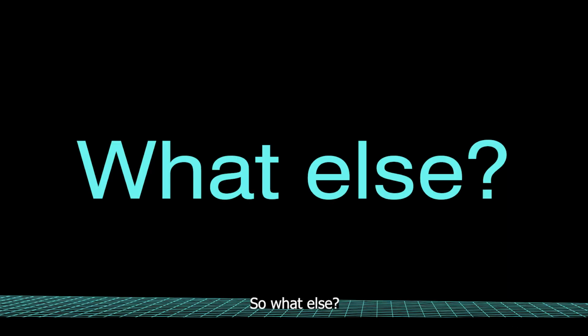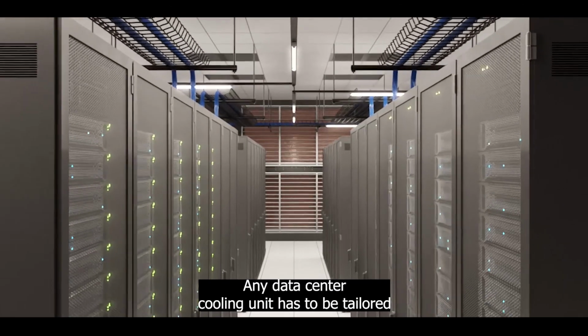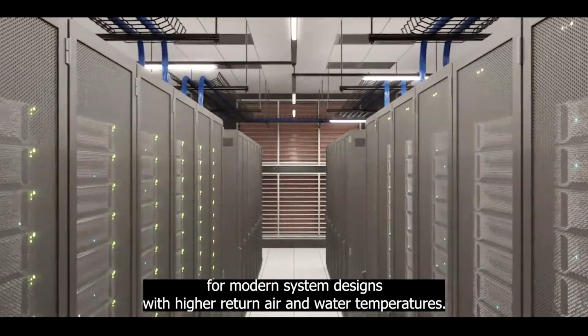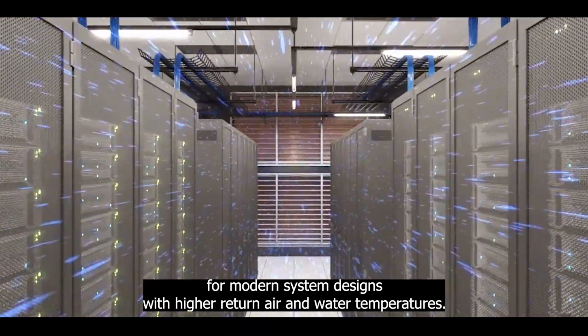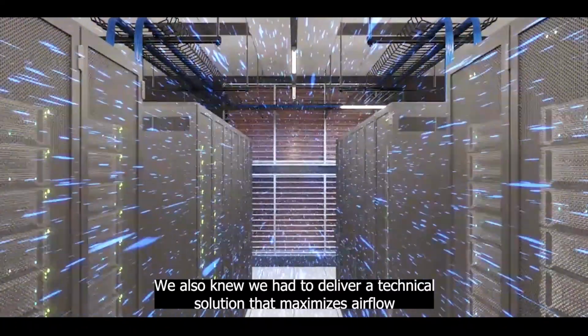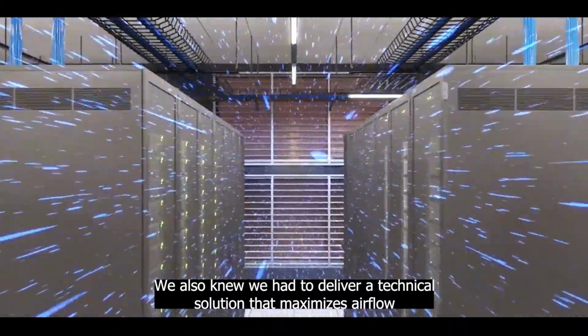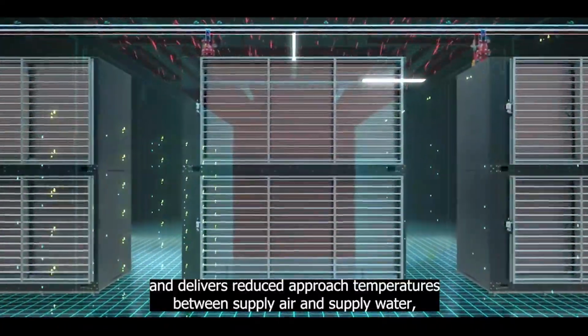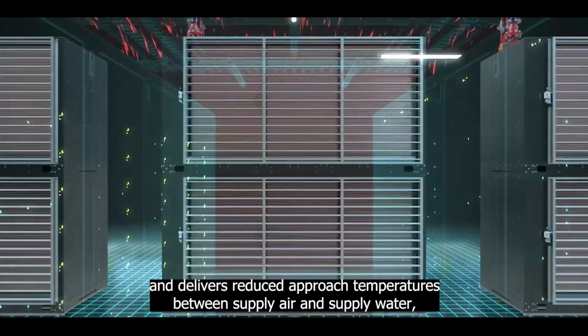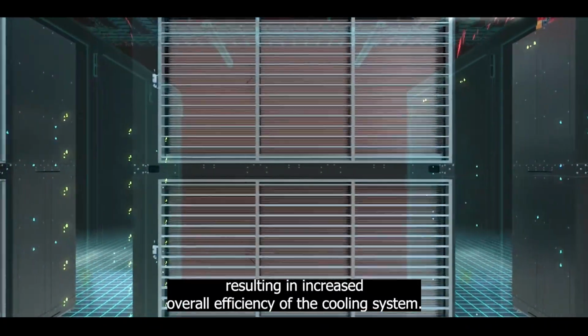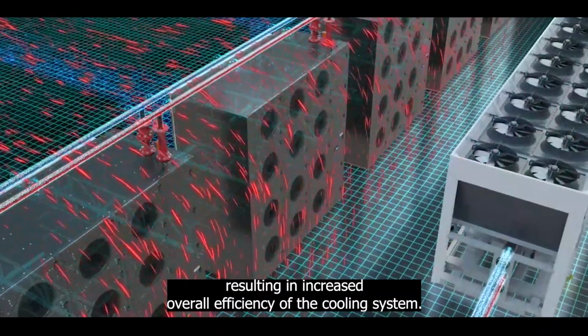So what else? Any data center cooling unit has to be tailored for modern system designs, with higher return air and water temperatures. We also knew we had to deliver a technical solution that maximises airflow and delivers reduced approach temperatures between supply air and supply water, resulting in increased overall efficiency of the cooling system.